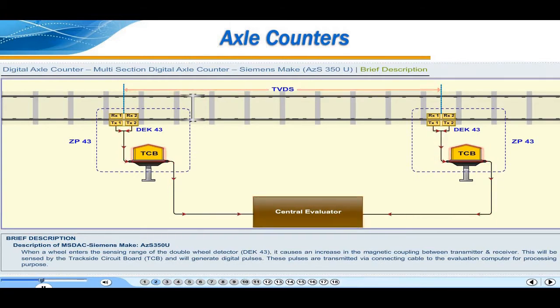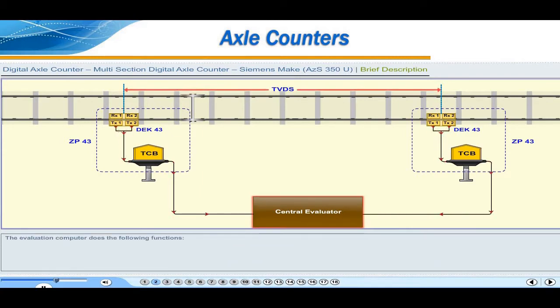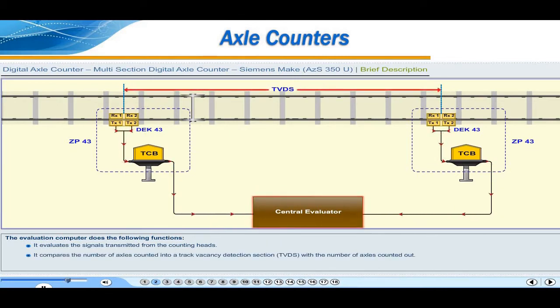This will be sensed by the trackside circuit board, that is TCB, and will generate digital pulses. These pulses are transmitted via a connecting cable to the evaluation computer for processing purpose. The evaluation computer does the following function. It evaluates the signals transmitted from the counting heads. It compares the number of axles counted into a track vacancy detection section, that is TVDS, with the number of axles counted out. It monitors the track vacancy detection sections and generates a track clear or occupied indication.